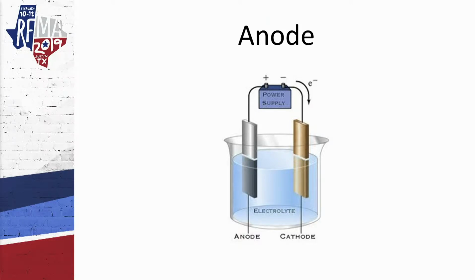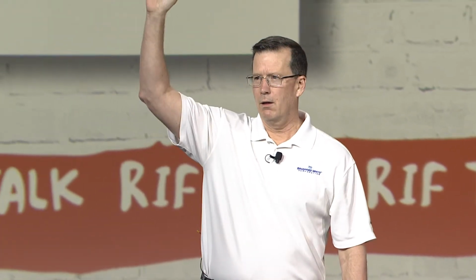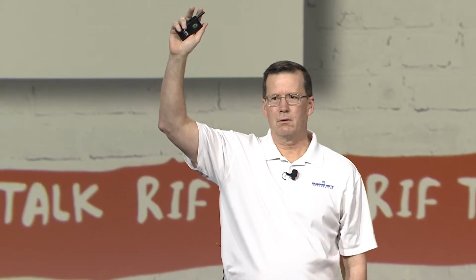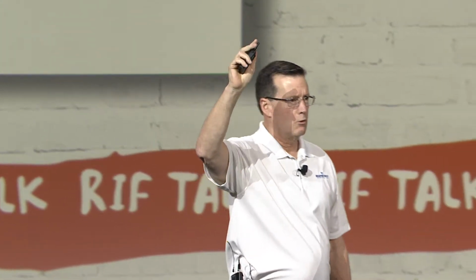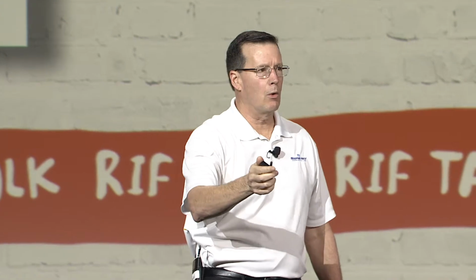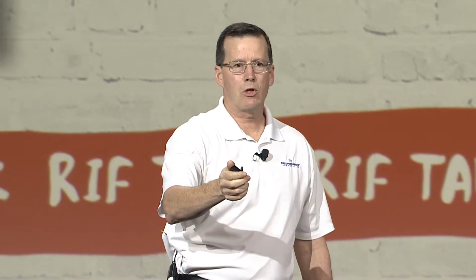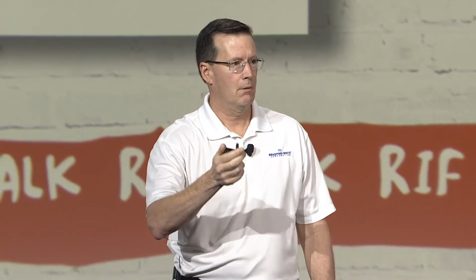By a show of hands from the PMs in here, how many people replace the anode rod? I see a couple, congrats, good for you. So the charge doesn't go away. Where does the charge go when the anode rod is gone? It starts to attack the tank, and that's a leak path. That is what's going to kill your tank.